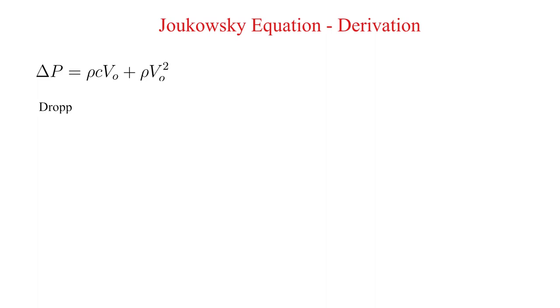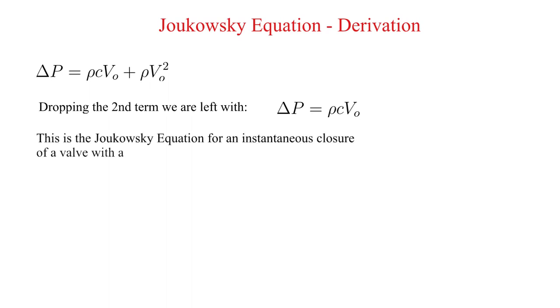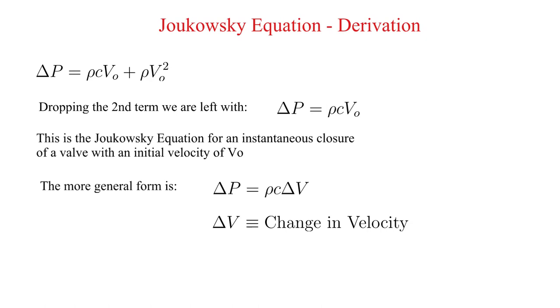Dropping the second term we are left with delta P is equal to rho times the celerity times V0. This is the Joukowsky equation for an instantaneous closure of a valve with an initial velocity of V0. More general form is delta P is equal to rho times the celerity times delta V where delta V is the change in velocity.